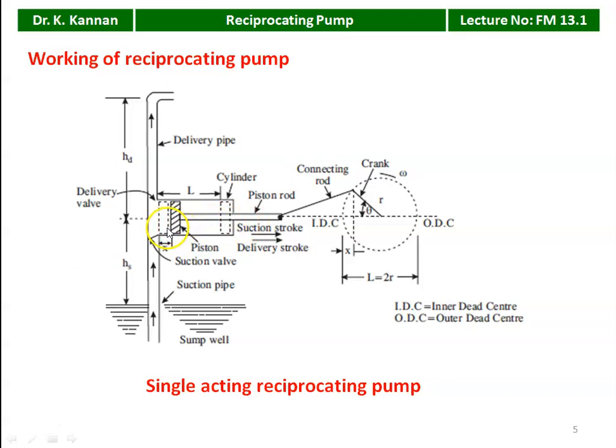When the piston moves from IDC to ODC (backward, toward the right side), vacuum is created, pressure decreases, the suction valve automatically opens, and liquid rushes into the cylinder. When the piston reaches ODC, the cylinder is completely filled with water. In the second stroke (delivery stroke), the piston moves from ODC to IDC (right to left). The delivery valve is closed initially; as the piston compresses the liquid, pressure increases, the suction valve closes automatically. When pressure further increases, the delivery valve opens due to pressure difference and water is supplied to the delivery pipeline and tank.